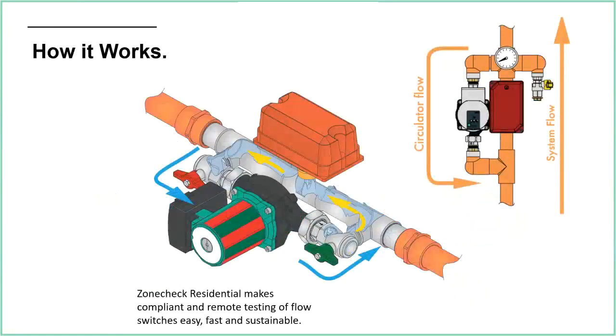That's a little cutaway version, just showing this idea of circulating the water. We simply suck water out from beyond the flow switch and pump it into the pipework before, and that creates this circle of water where we're actually testing the flow switch using water under the correct conditions, which is one head in operation. We're activating the paddle and checking that the flow switch is working correctly.